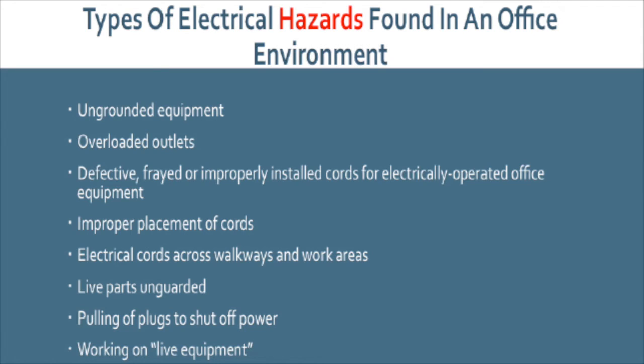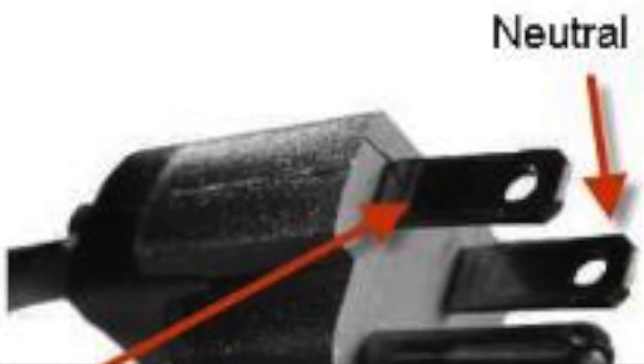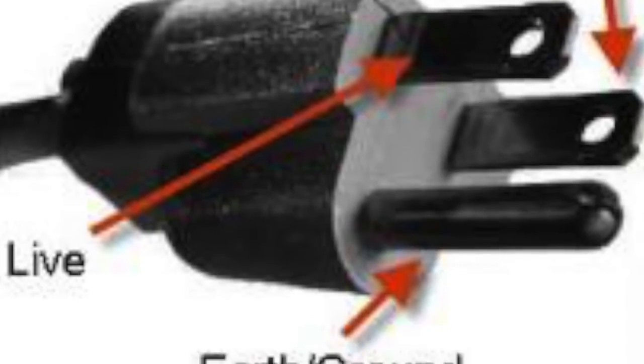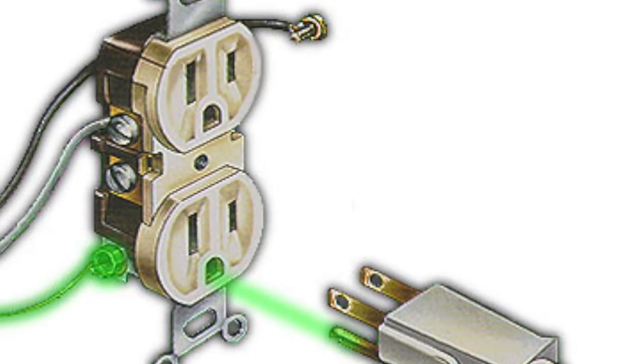Most fixed equipment, like large stationary machines, must be grounded. Equipment connected to electricity by cord and plug absolutely must be grounded if, one, located in hazardous or wet locations, two, if it's operated at more than 150 volts to ground, or three, if it is a certain type of equipment such as refrigerators and air conditioners. In any case, never remove the third grounding prong from any 3-prong piece of equipment.